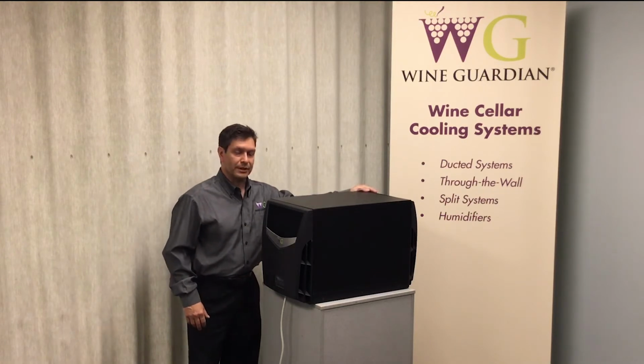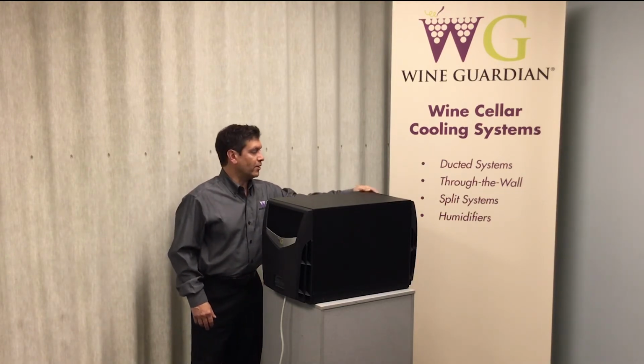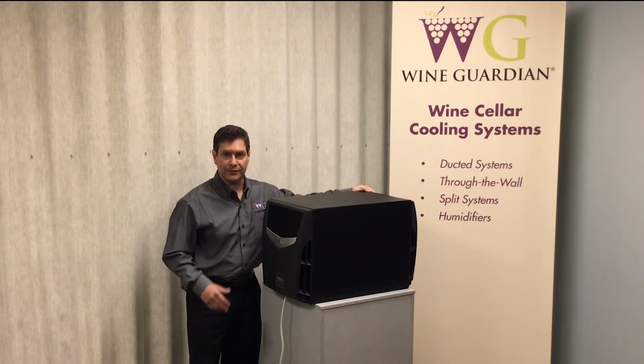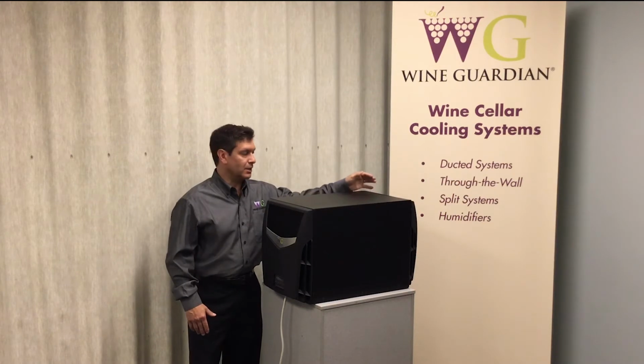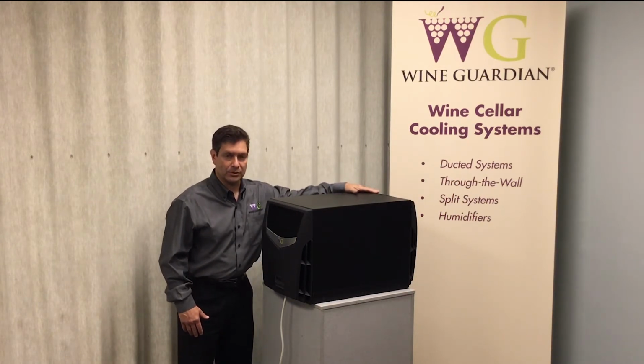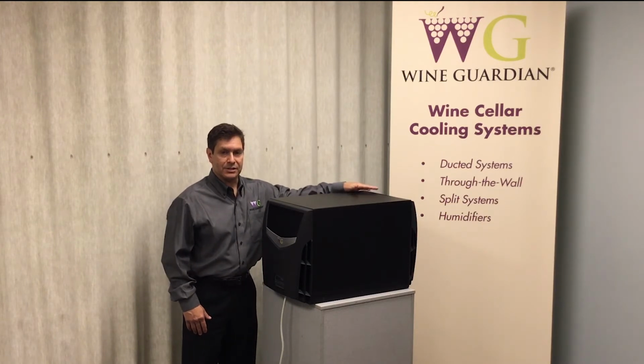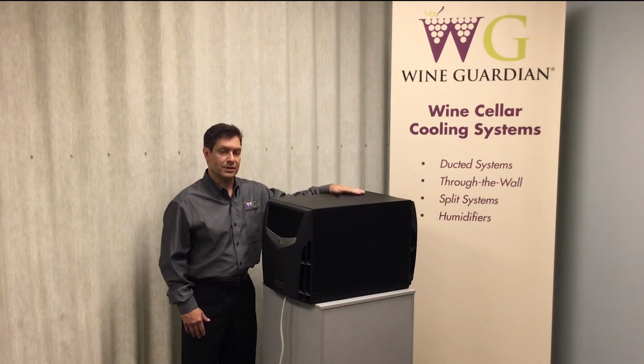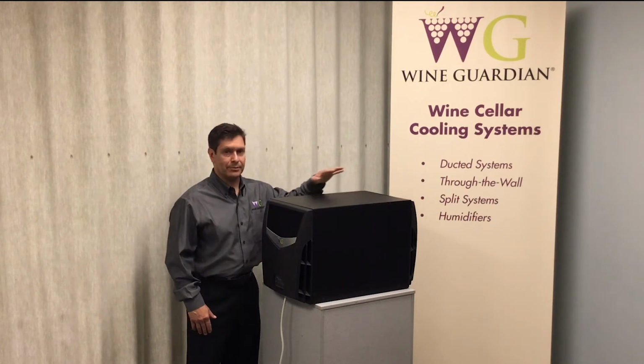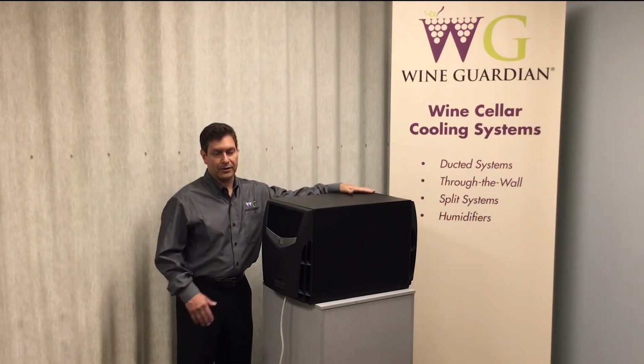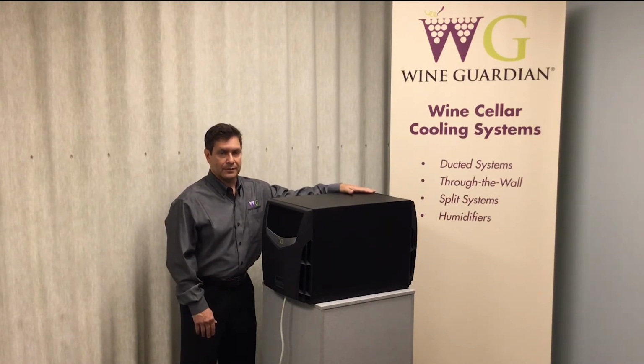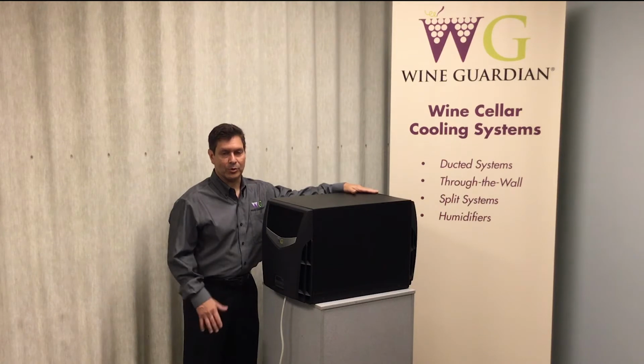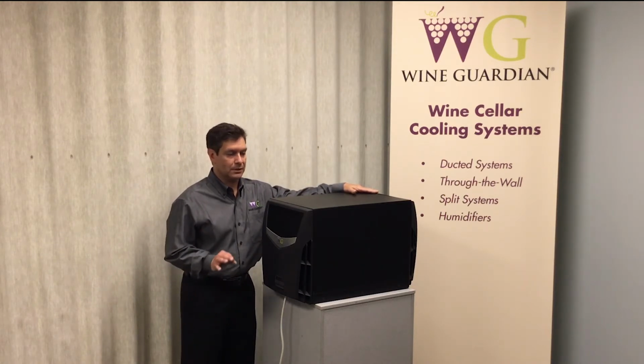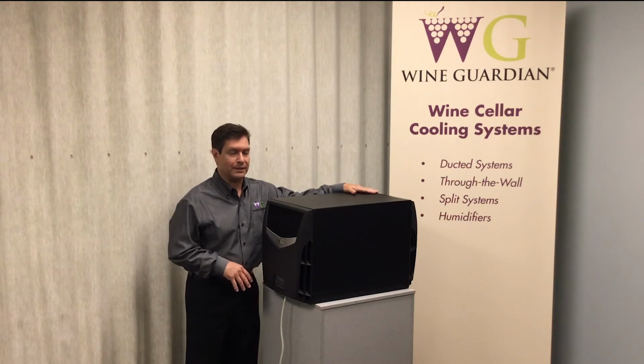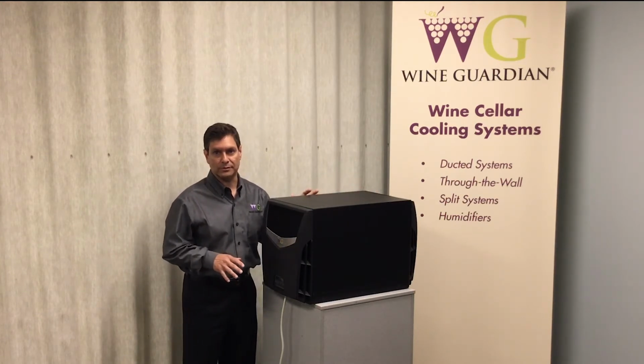On the condenser end of the unit, it's important to understand where this unit will be venting into. I mentioned a finished basement or a mechanical room or crawl space. You really should understand how much room you have available for venting and the conditions of that space in which you're venting into. This device is designed to be mounted indoors generally, so maximum and minimum conditions for this mounting area are anywhere from a low of 50 degrees Fahrenheit. This will actually handle up to 115 degrees Fahrenheit, but we recommend 90 to 95 degrees as an optimal condition where this unit can be mounted and successfully keep your wine cellar cool.